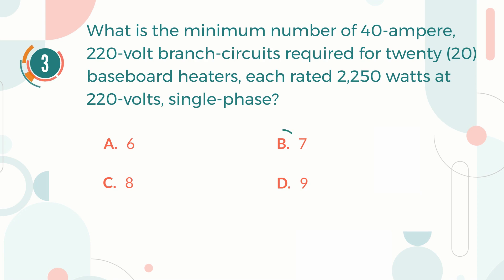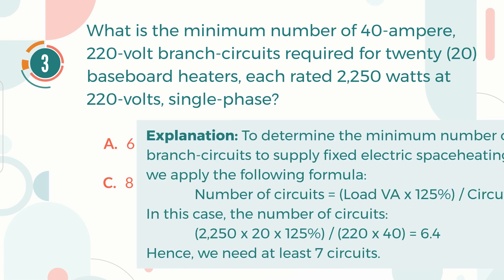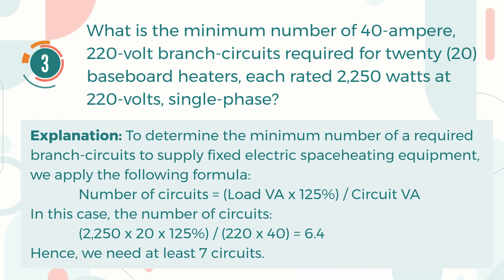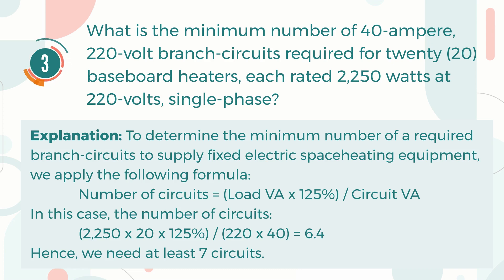The correct answer is B. 7. Explanation: To determine the minimum number of required branch circuits to supply fixed electric space heating equipment, we apply the following formula: number of circuits equals 1.25 times the load in volt-amperes or watts, divided by the circuit in volt-amperes or watts. In this case, we get 6.4, which must be rounded to the next integer. Hence, we need at least 7 circuits.